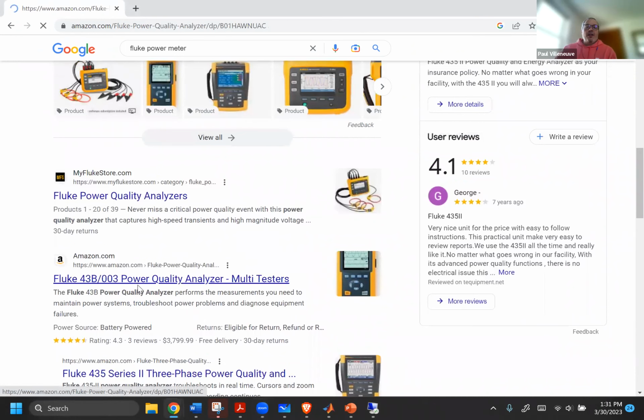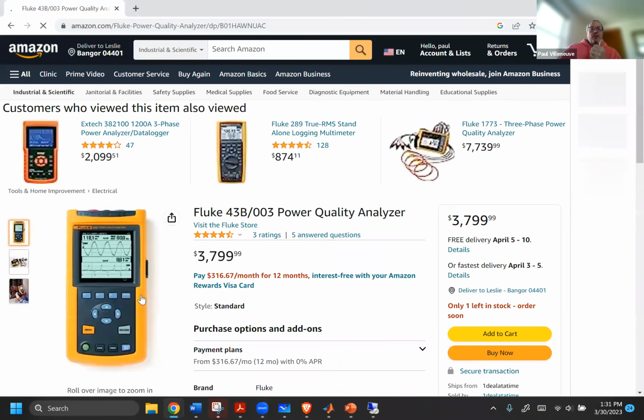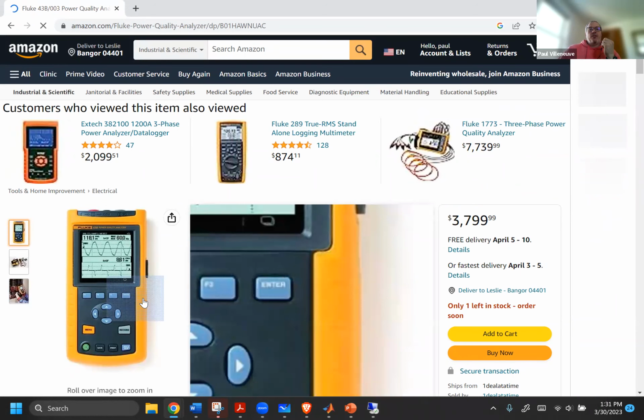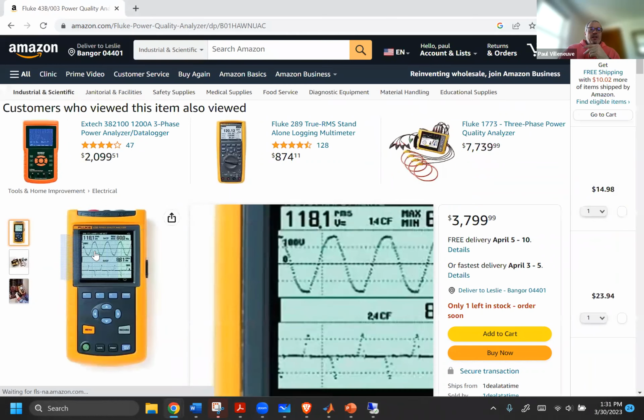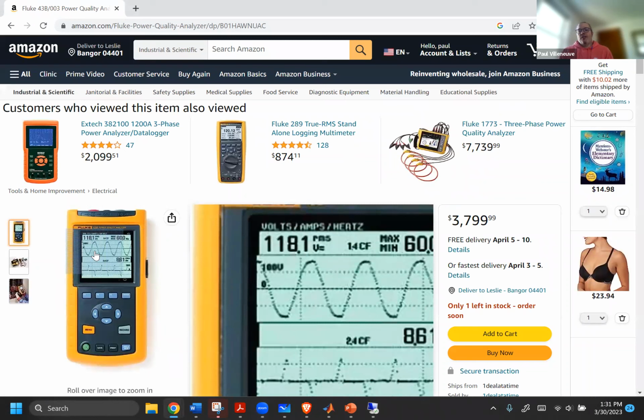This is power quality, but how do you measure power? You measure the voltage and the current, and you just get the waveform phase shift and it calculates watts. So like almost every electrical component that you have, you just measure the voltage and the current. And then you get power. But wouldn't that also be able to give you, if you know the phase shift, your apparent power, like power factor?